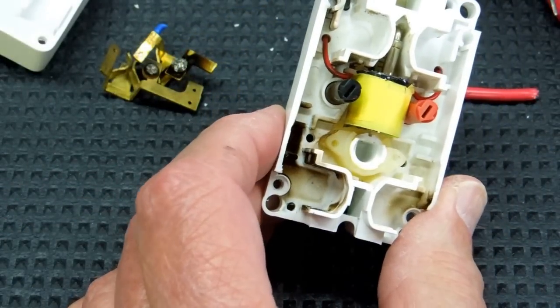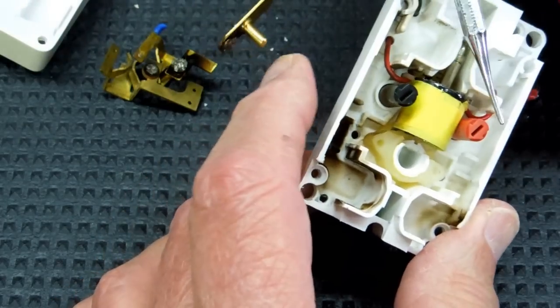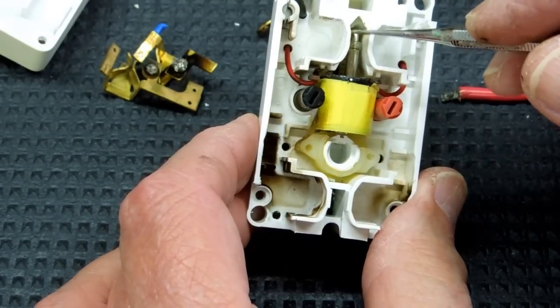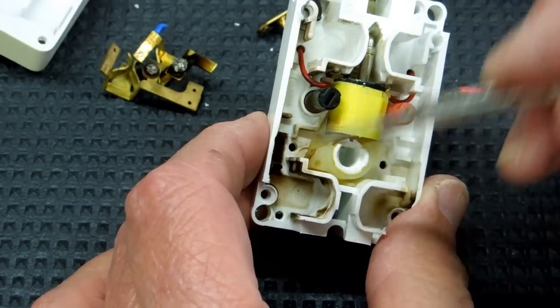Pull out the other side of the contacts. They're burnt as well. Interesting the way this would work. This cam lobe would operate on this pin on both sides. The solenoid would trigger one way, and it would allow the contacts to close.